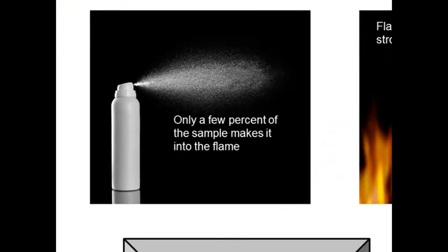One thing you have to do is nebulize your sample, turn it into a spray of little tiny droplets. And if you have too many big droplets out of that spray, then they never evaporate and you never get them into the flame. In fact, in AES spectrometers, you may only sample two to three percent of the total sample you're putting in.